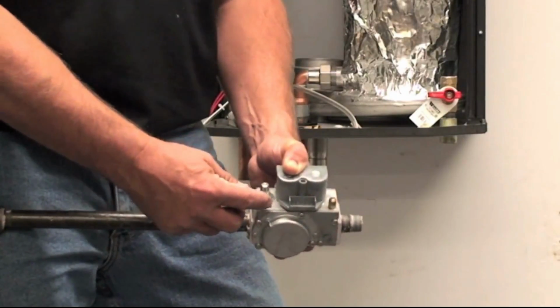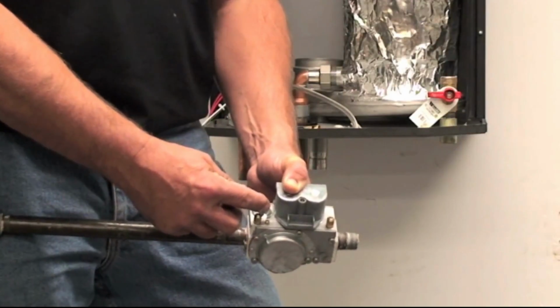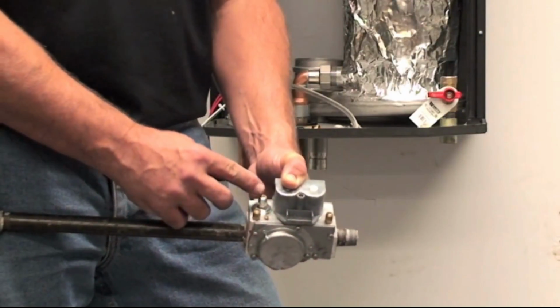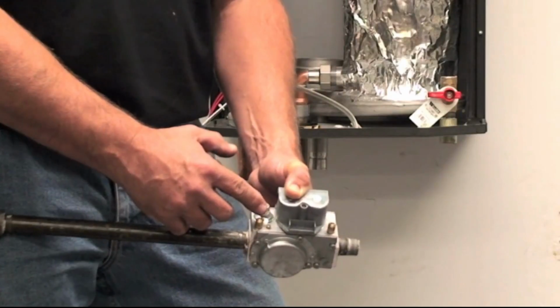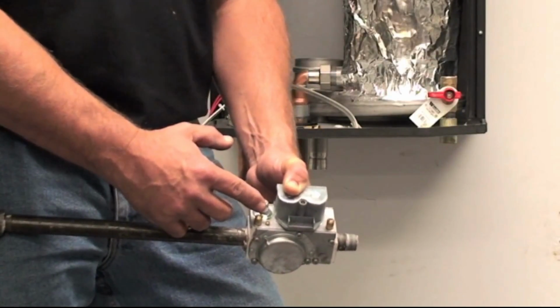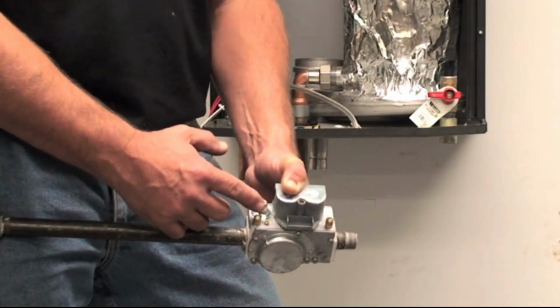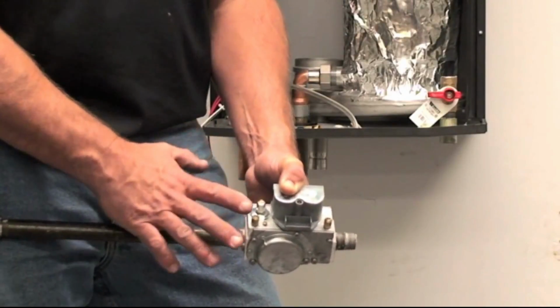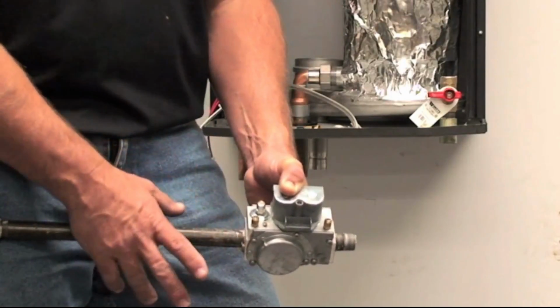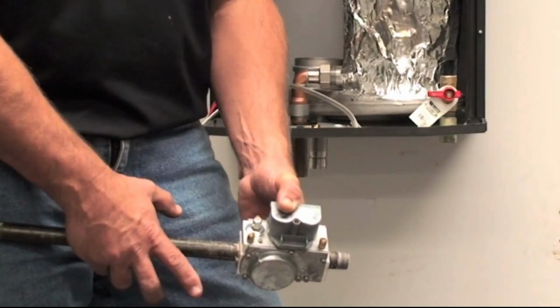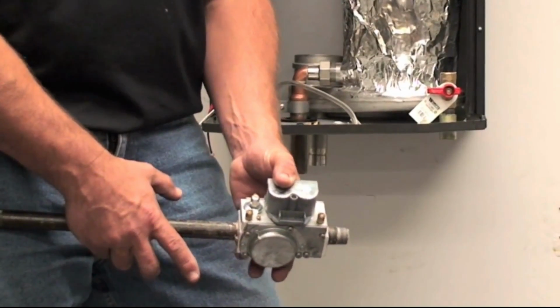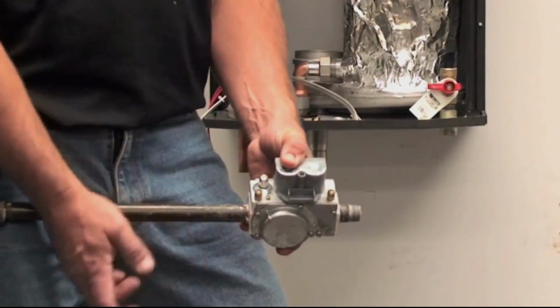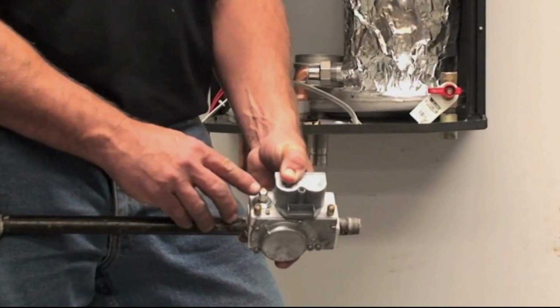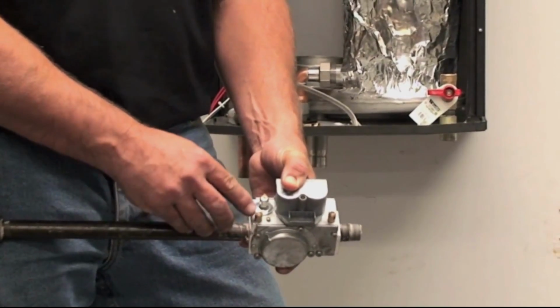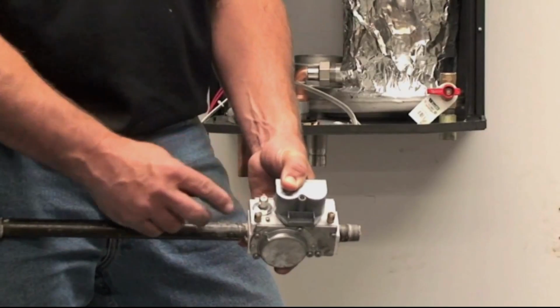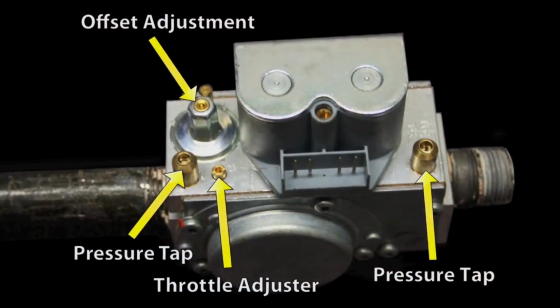So if I'm turning the valve left to increase fuel on my throttle, I've got to turn it right to increase fuel on my offset for light off. You need to have combustion equipment whenever you're doing adjustments. It's very important on either natural gas or LP to make sure that your combustion is running clean and safe. When you're doing your offset adjustment, you also want to open this needle valve again, which is on the outlet of the valve, and you can make those adjustments.